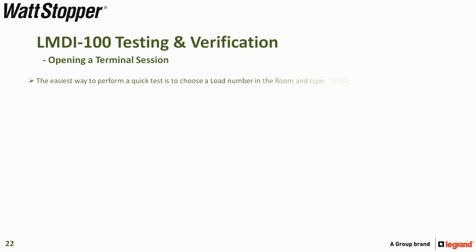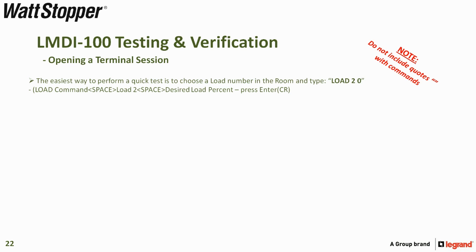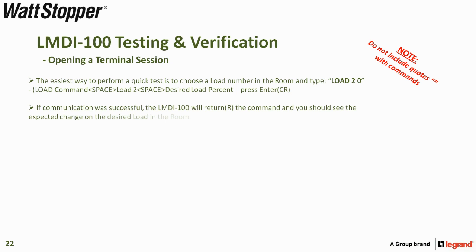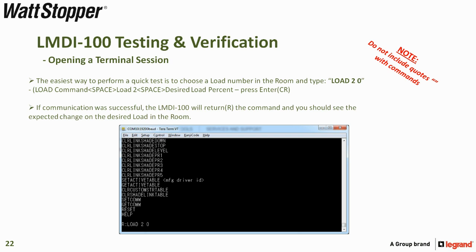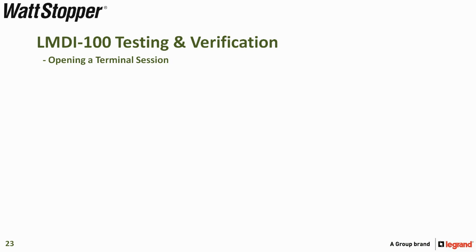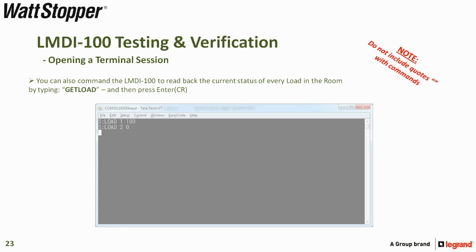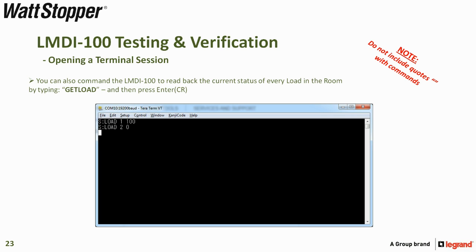The easiest way to perform a quick test is to use the load command. For example, type 'load 2 0', which will drive load number two to zero percent. After pressing the Enter key, and if communication was successful, the LMDI100 will return the command and you should see the expected change on the desired load in the room. You can also command the LMDI100 to read back the current status of every load in the room by typing 'get load' and pressing Enter. This will return every load in the room as well as their percentage.